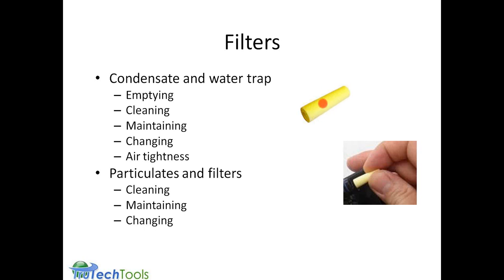that's a signal to change the filter. So you can simply remove the filter cap at the end of the probe. It's a bayonet-type clear window, and pull the filter out and examine the base of it. If it's bright yellow and the top is gray, then that means it needs to be replaced with a new filter.